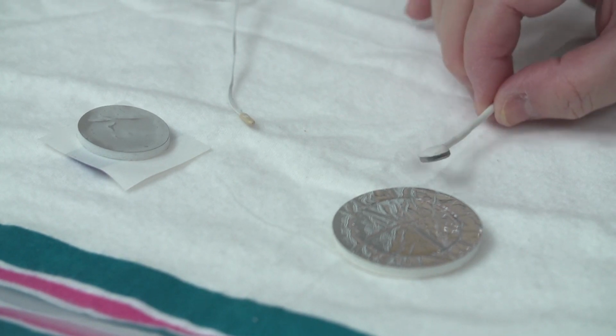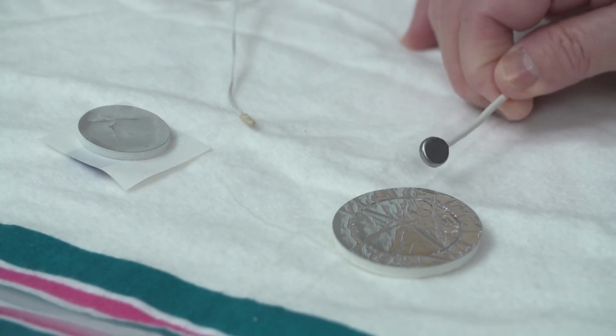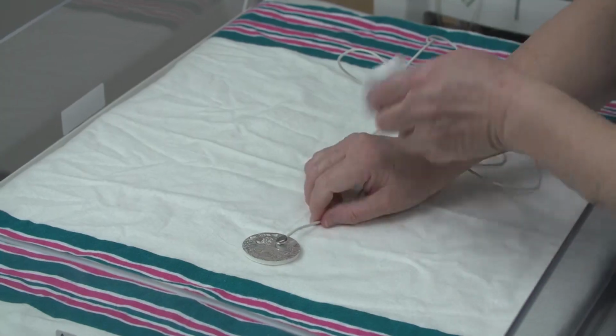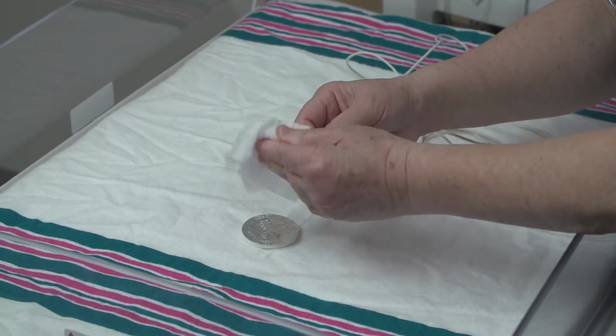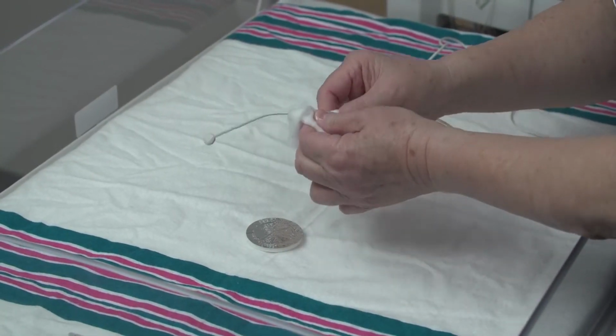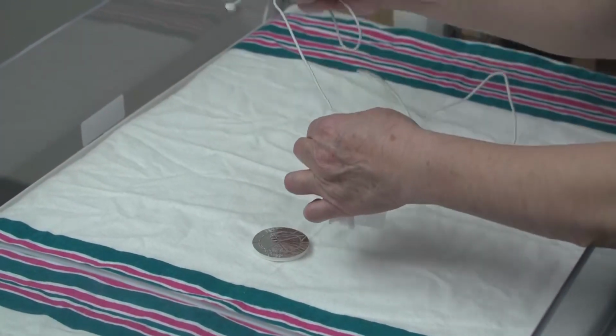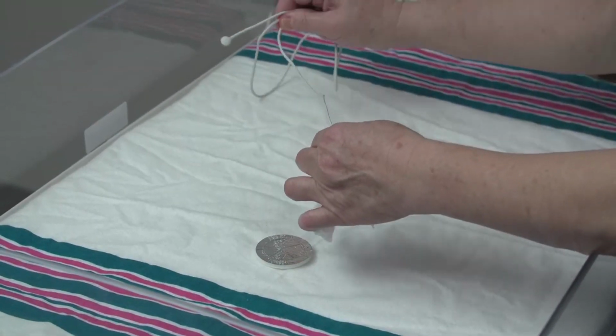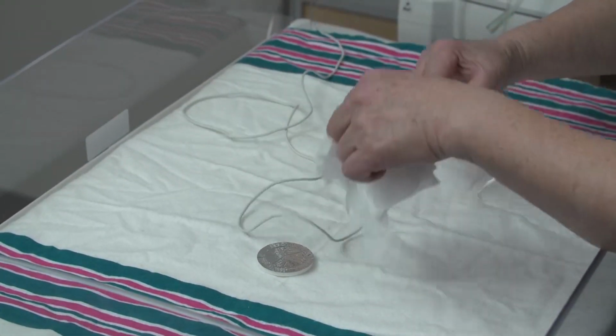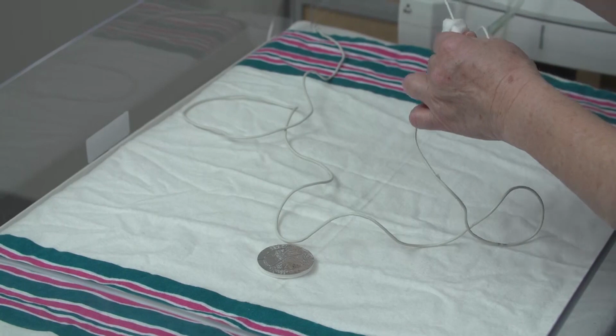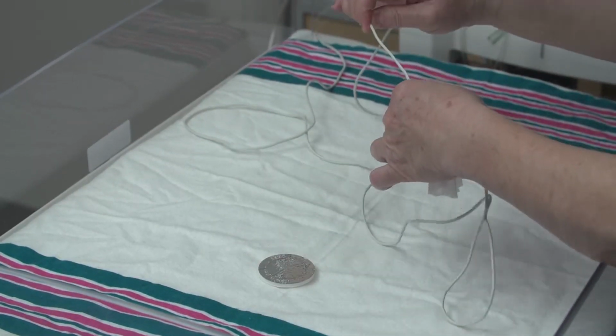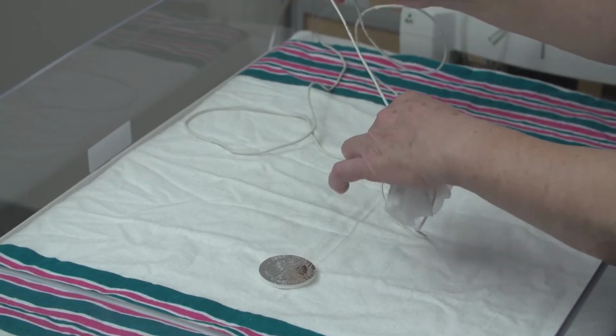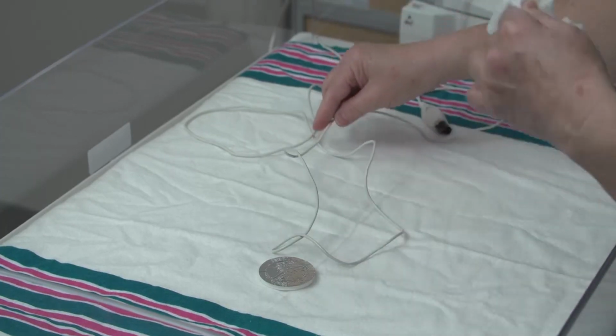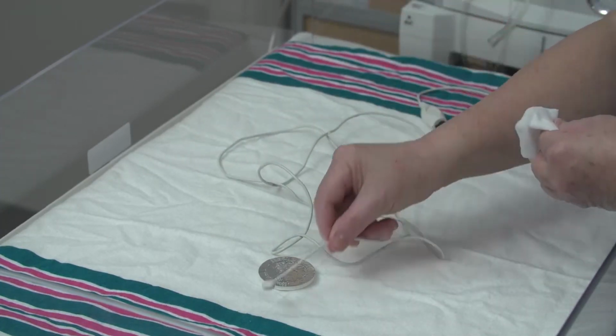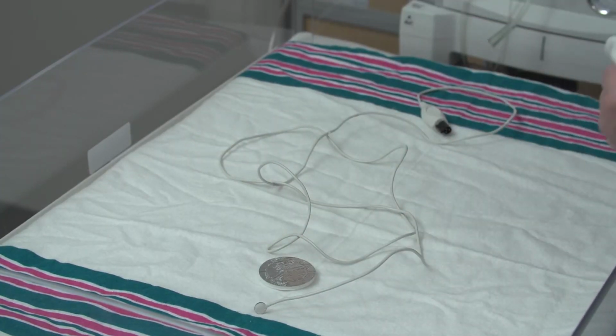The reusable probe has a round metal disc at the patient end. Remember, when wiping clean, start at one end of the probe, the tip or the plug, and clean the probe by moving the cloth towards the middle of the probe cord to the other end. Do not start at the middle of the cord and move the cloth towards the plug or tip end of the probe. This may stress the connection between the cord and the tip or plug due to an abrupt stop when reaching the tip or plug.